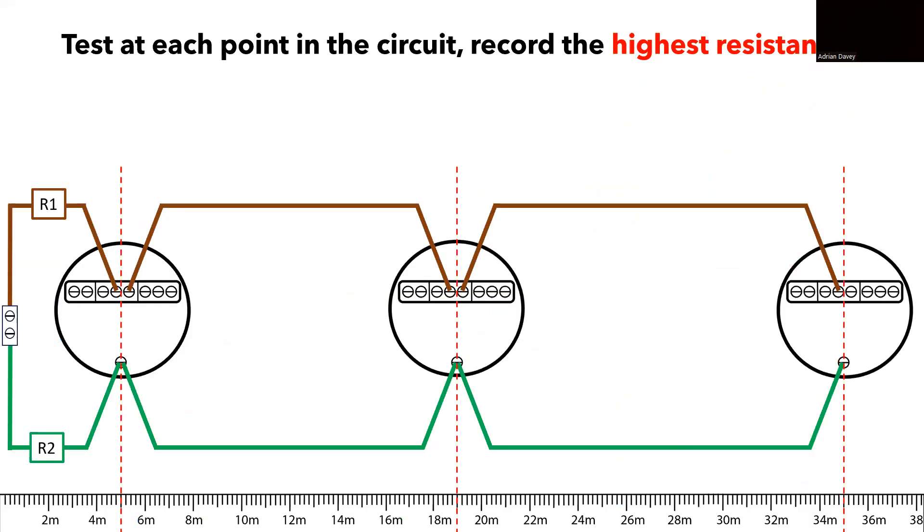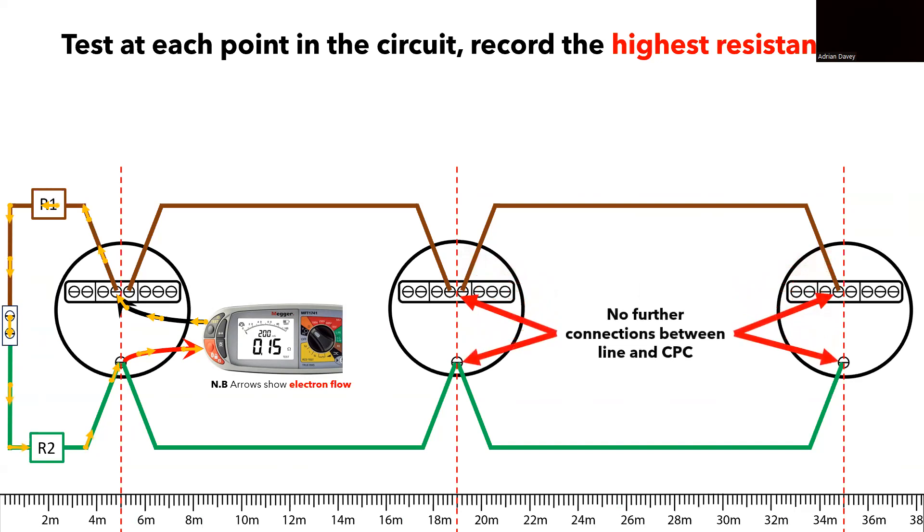Once we connect the low ohm continuity meter into the circuit, the MFT bridges the line and CPC, creating a closed loop. This allows electron flow from the MFT's batteries starting at the negative terminal. The electrons travel around this small circuit we've created, and return back to the meter with a positive terminal and into the battery. The meter then measures the electron flow passing through the MFT and uses Ohm's law to calculate a resistance of 0.151, displaying it on the screen. Since there are no other connections between R1 and R2, there can be no electron flow further into the circuit, therefore we are only measuring this small closed loop upstream of the first pendant. A small loop should produce a small resistance.